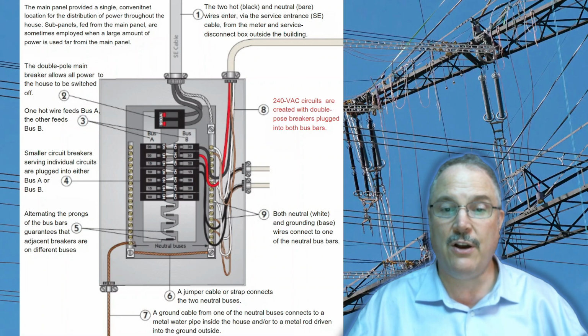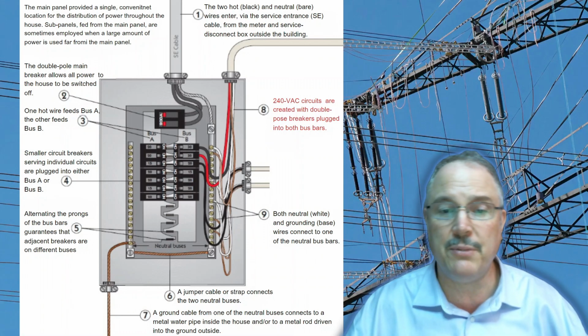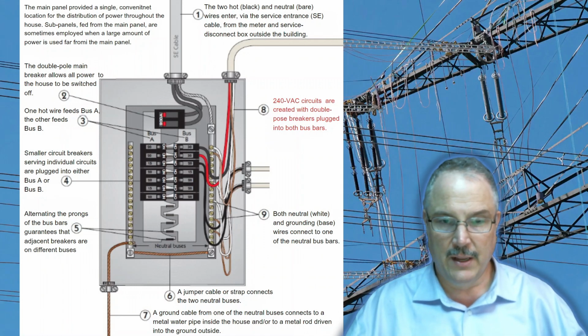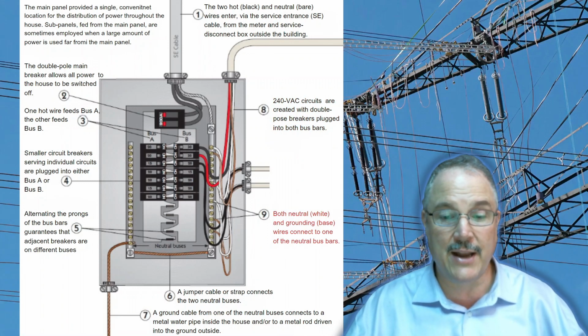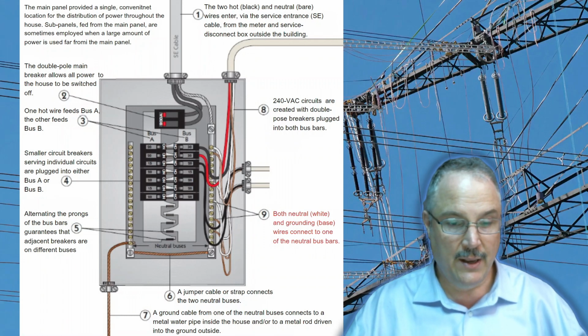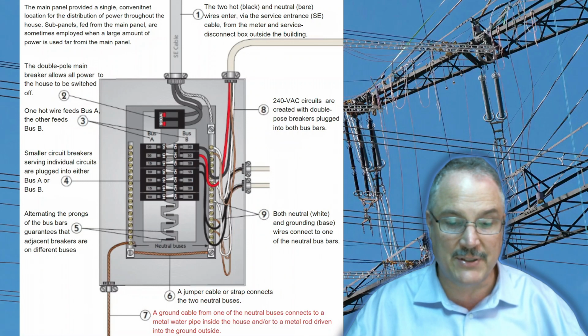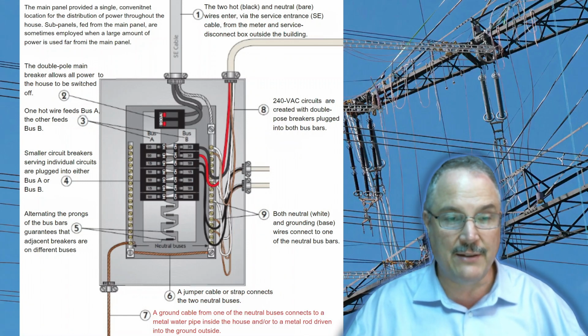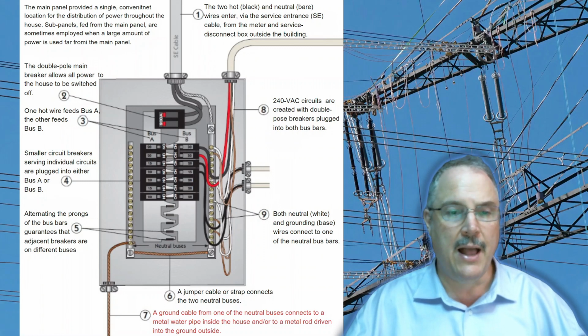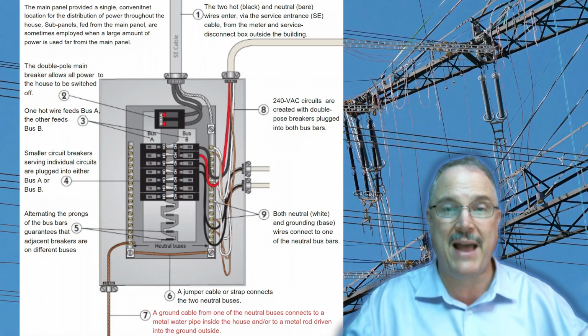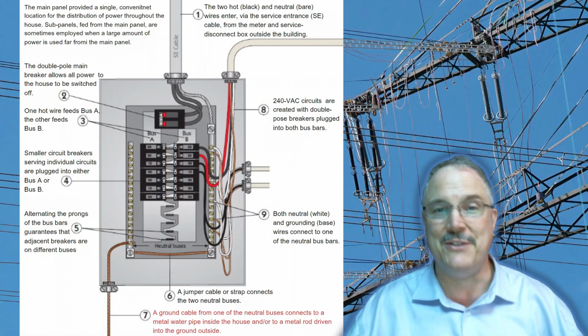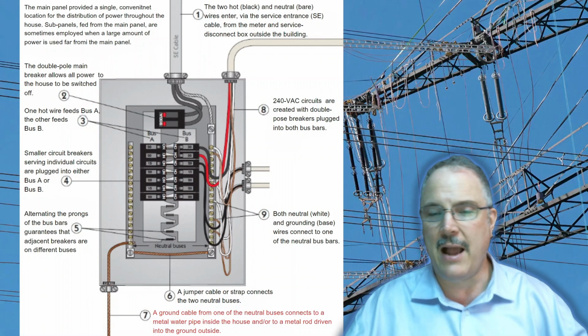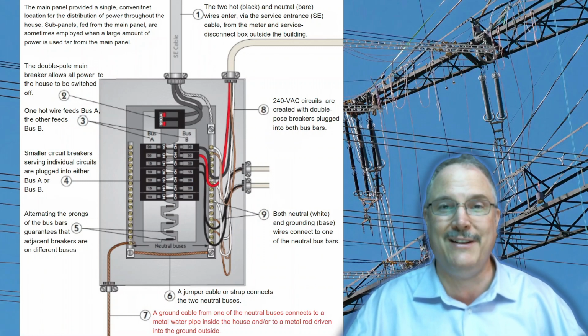240 volt circuits are created with double pole breakers plugged into both bus bars. Both neutral white and grounding bare wires connect to one of the neutral bars. A jumper cable or strap connects the two neutral buses, and a ground cable from one of the neutral buses connects to a metal water pipe inside the house or to a metal rod driven into the ground outside. It's very important to have your electricity grounded, and everything in the house is going to go through the main panel here, and it's really critical that this main panel is grounded properly. I didn't prepare a slide to show what that looks like if it's not, but it's dangerous. You got to be grounded.